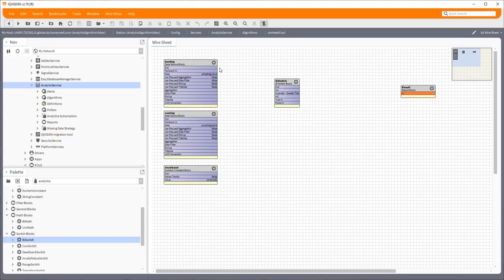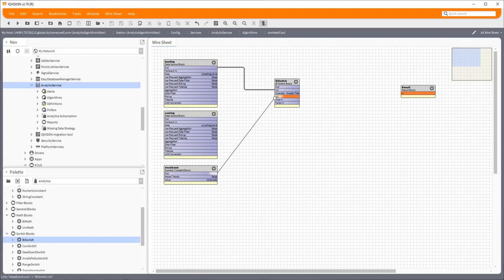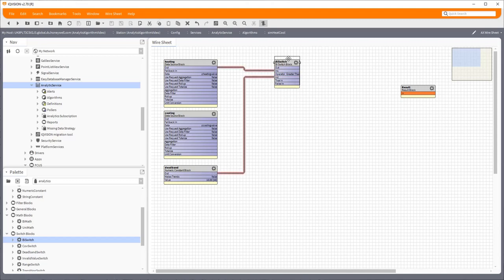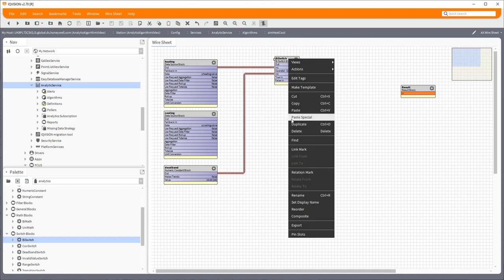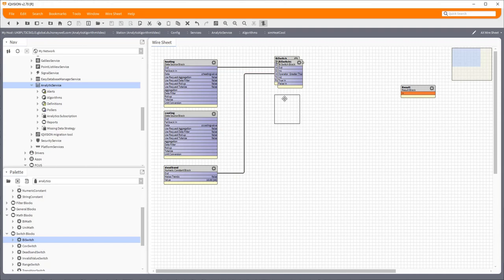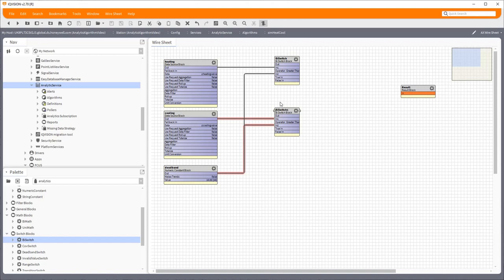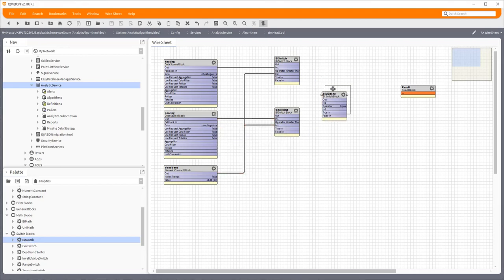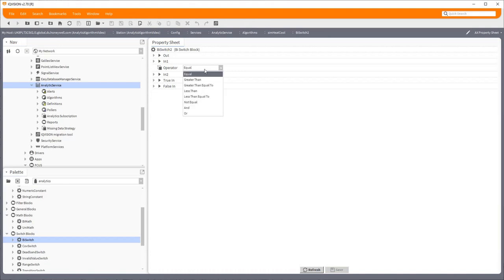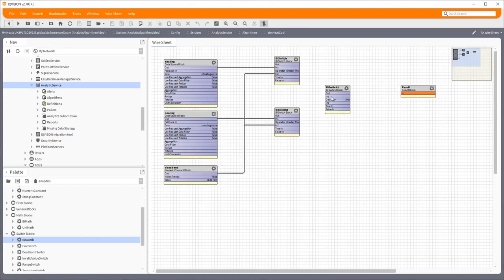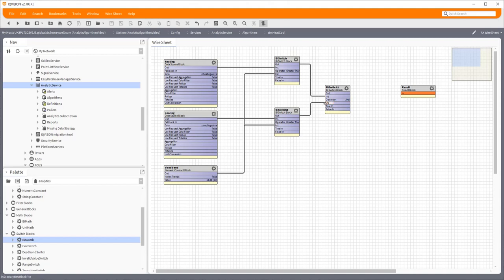So this particular one is going to be greater than or equal to. So I want a yes it is, if the heating valve is greater than or equal to 10 percent open. Now I also want to know exactly that same bit of information for the cooling valve, so we'll do the same thing, just duplicate it in this particular instance. Now for my analytic I need both of those things to be true for this to be a problem, so both valves open more than 10 percent. So we have one final switch block, and this point it's going to be and, so both of them are open. We just feed both of those in. Final bit you always have to have is to link to the result block for that algorithm. So there we go, that's our algorithm done.